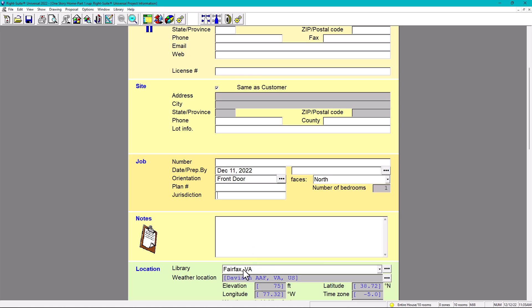The weather location is very important because that depends on the location — it's going to give you the outdoor design temperatures. What is most important in the project information is the weather location, because that's going to decide what your outdoor design temperatures are. You don't want to make a mistake there.